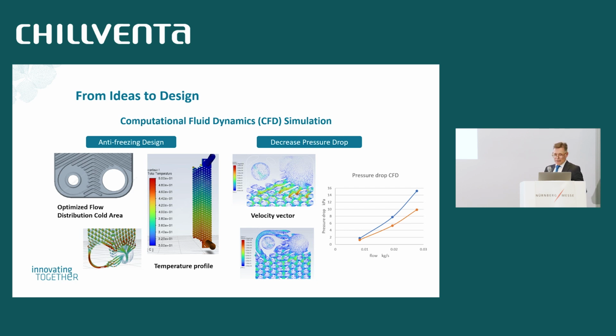With this tool, you can design different types of plate patterns, and you can see how this plate pattern will function. For example, one case where we use it a lot is for anti-freezing design, because you don't want to have freezing inside the brazed plate heat exchanger, then you will destroy it. Today, the heat pump manufacturers would like to go tighter and tighter on the temperatures, and therefore it's a must to be sure that you have a heat exchanger that will not freeze.